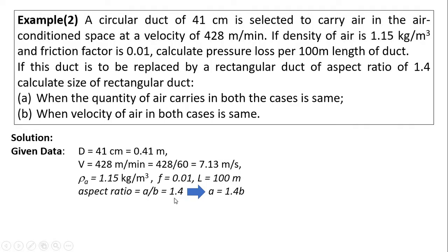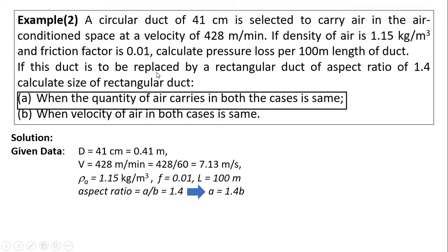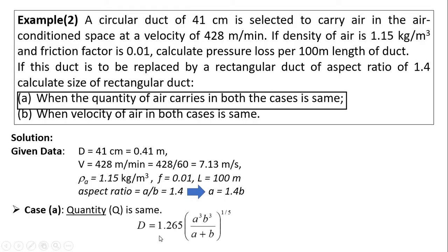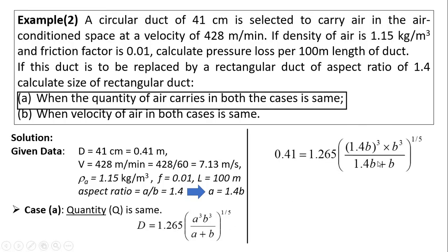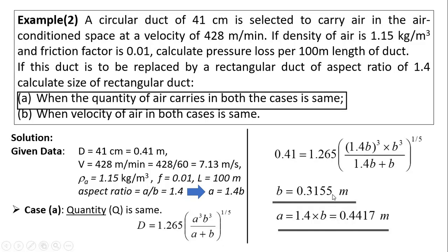With aspect ratio a/b = 1.4, we can write a = 1.4b. For the first criteria — when quantity of air is the same in both ducts — we use the equivalent diameter formula. Diameter D is known; a is expressed in terms of b, so the only unknown is b. Solving gives b = 0.3155 m, and substituting back: a = 1.4 × b = 0.4417 m.